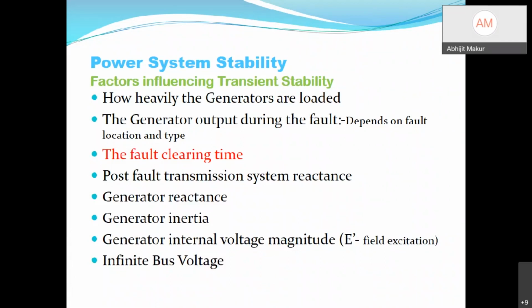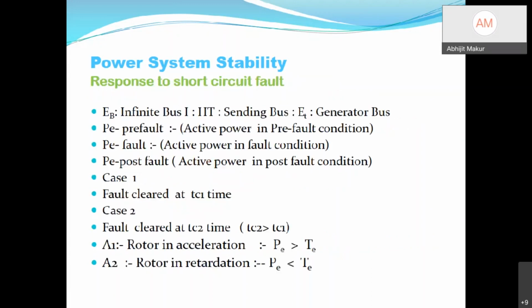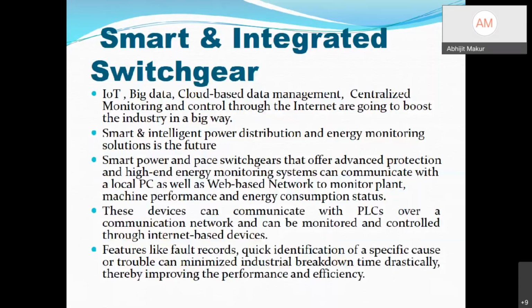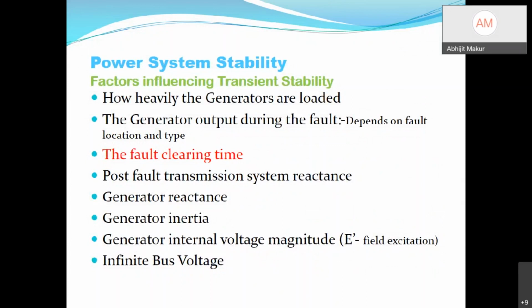Now, power system stability. I think I want to skip this one as the time is short. The only one thing I want to say is, let's go to the previous slide. Just the previous slide. The fault clearing time. Fault clearing time is one part that is very important. If the fault clearing time is not within a certain limit, then the generation can go out of step, because most of the generators that we use are alternators that have a DC magnetizing excitation, and if the torque angle delta increases beyond a certain limit, then the system will go out of step. Next.